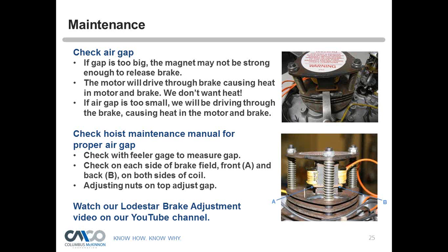So you want to take a feeler gauge, okay? And in the feeler gauge here, you can see the brake field. You want to check it on each side of the brake. You want to check in the front. You don't want to stick your feeler gauge all the way through. You want to check it in the front here. You want to check it in the back. And then same thing on the other side of the brake field. You want to check it again on the other side.